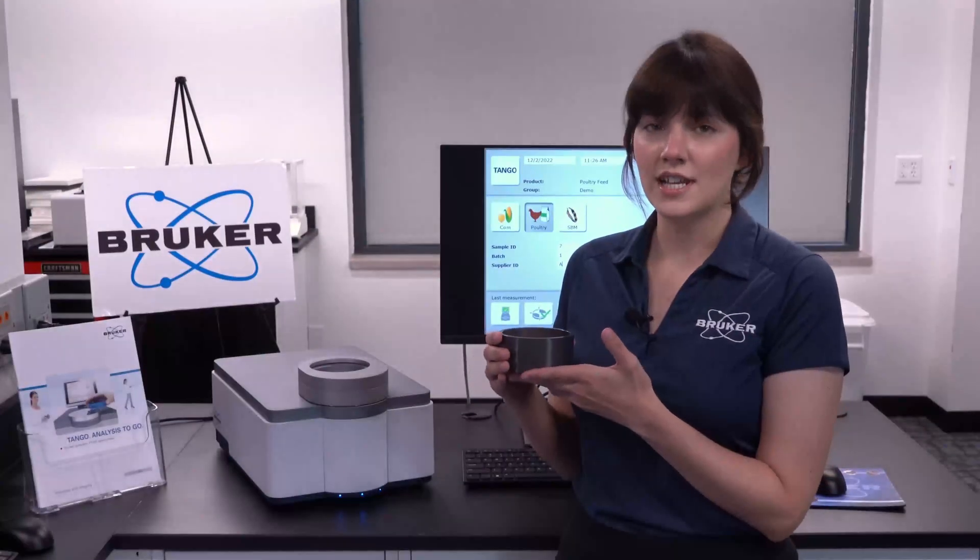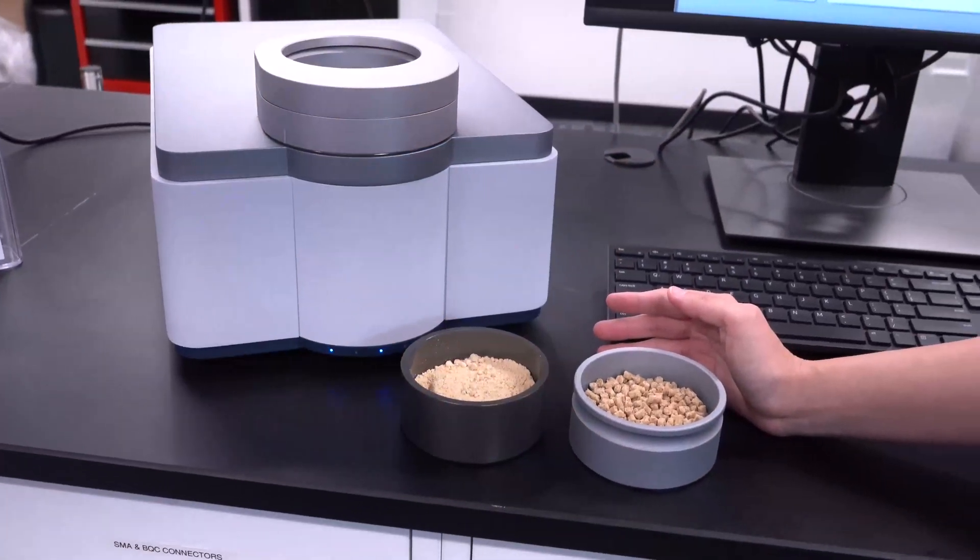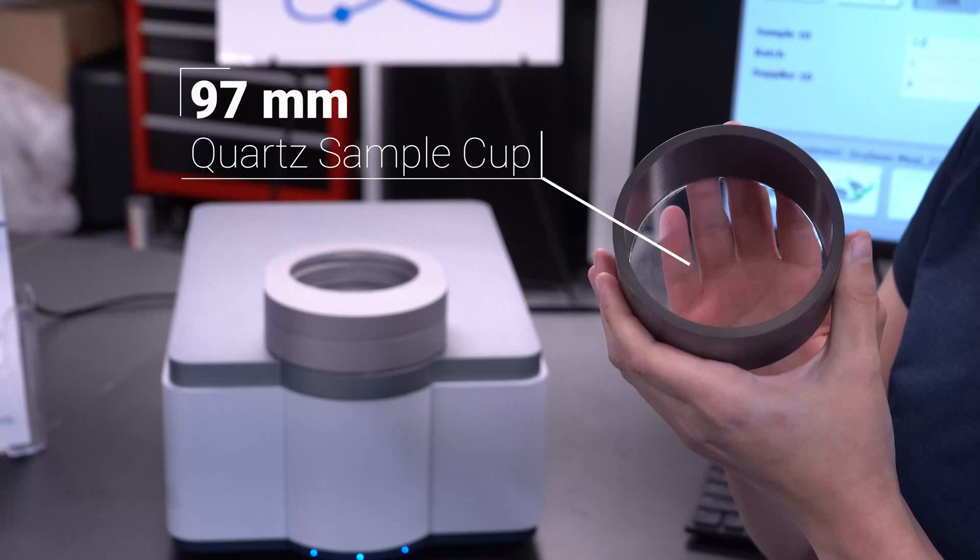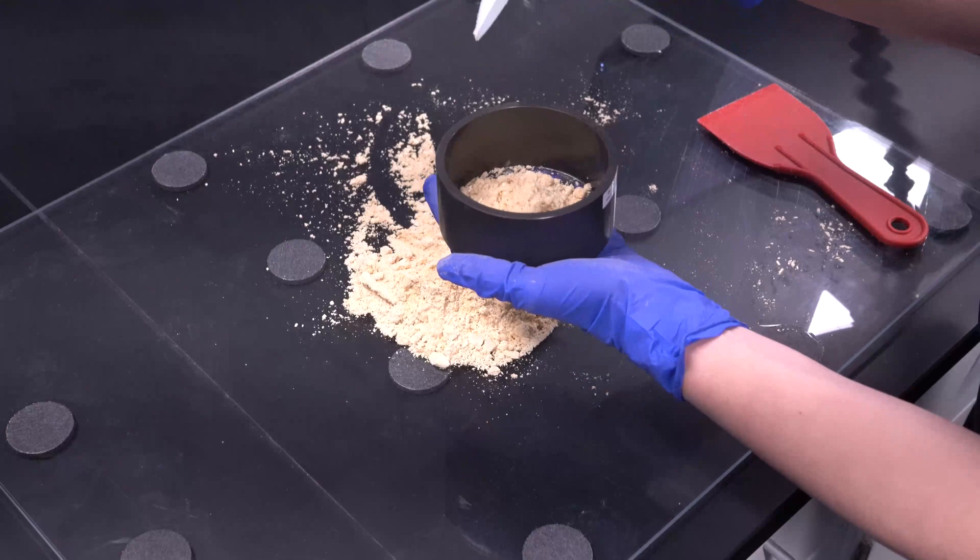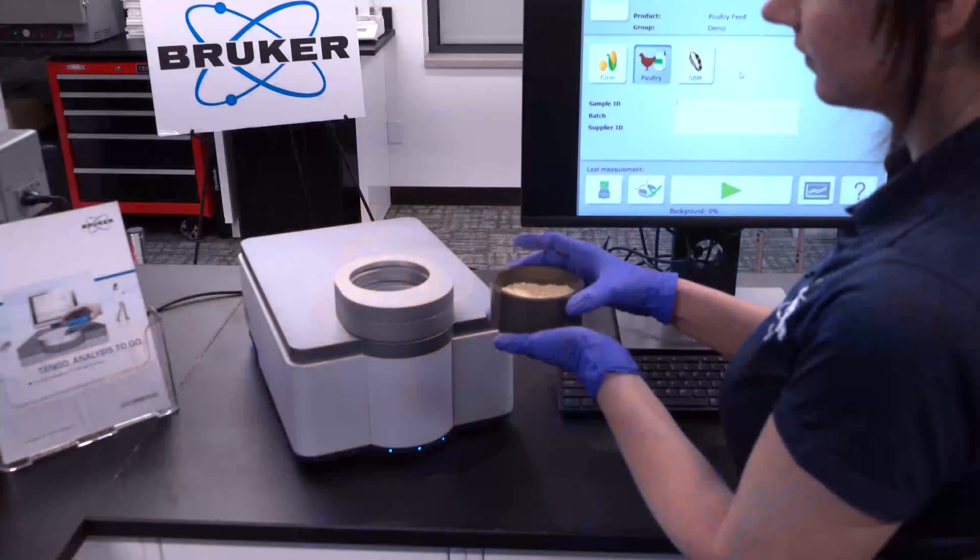So let's take the Tango for our test drive and see how this works for our ground sample versus samples that are still in pellet form. We're going to be using a 97mm cup with our rotator accessory as it has a greater surface area presented to the light and thus we get a better representation of our entire sample. We filled the quartz cup with enough sample such that there is no light showing through to the bottom of the cup. And now we can simply place it on the rotator.